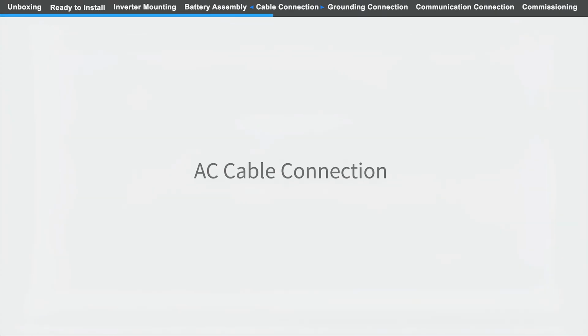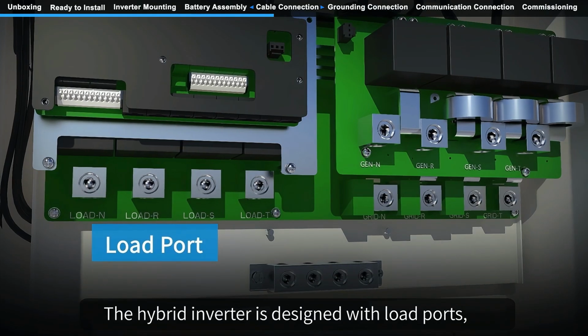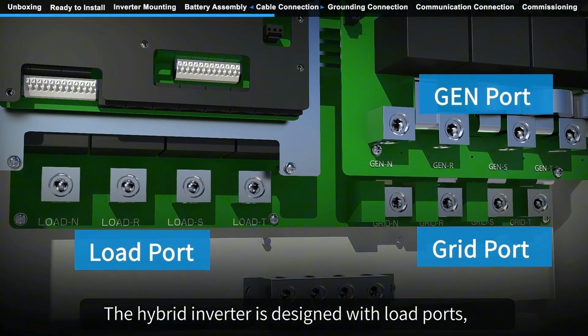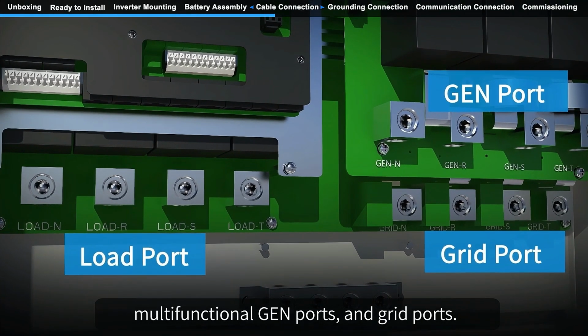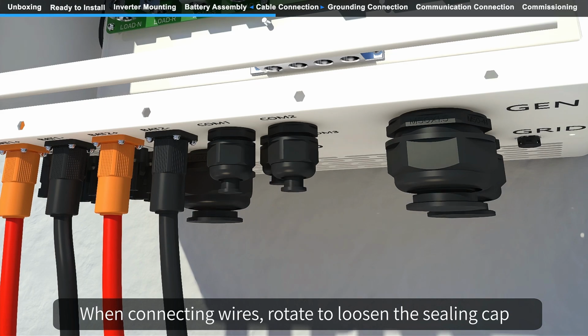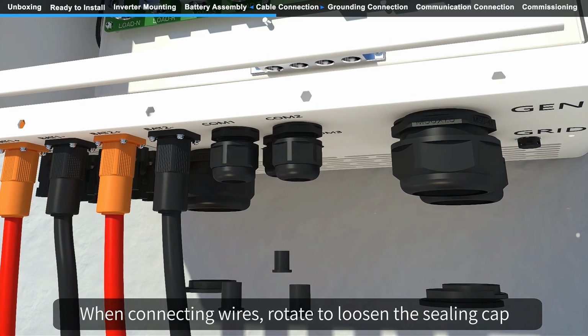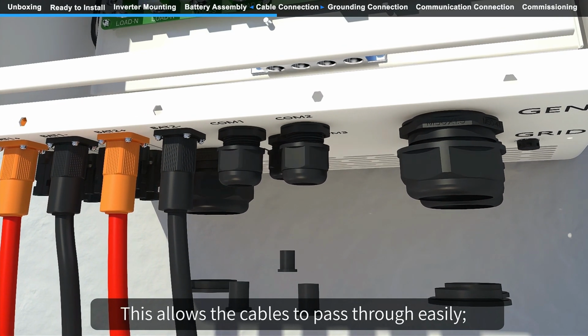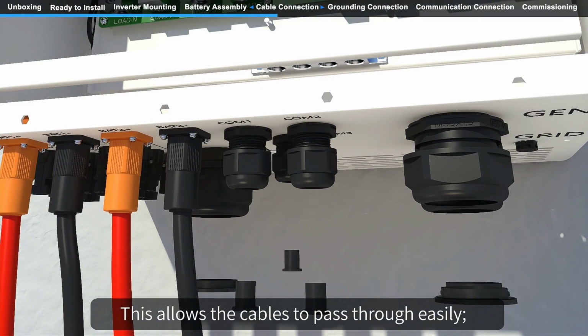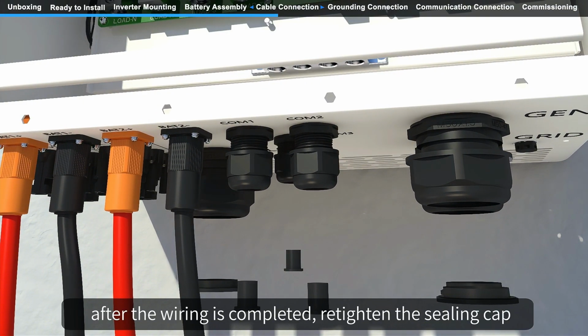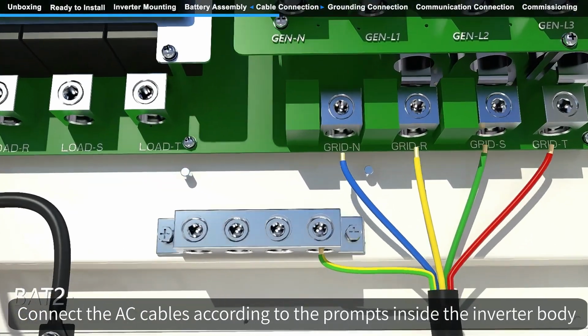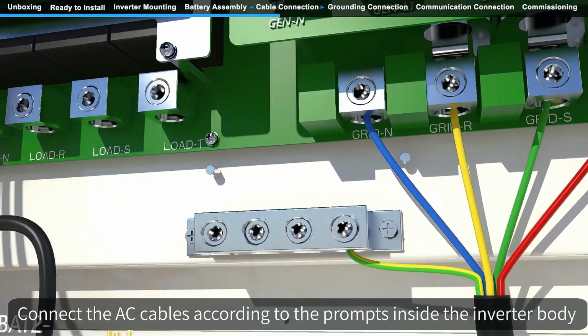AC cable connection. The hybrid inverter is designed with load ports, multifunctional gen ports, and grid ports. When connecting wires, rotate to loosen the sealing cap. This allows the cables to pass through easily. After the wiring is completed, retighten the sealing cap. Connect the AC cables according to the prompts inside the inverter body.